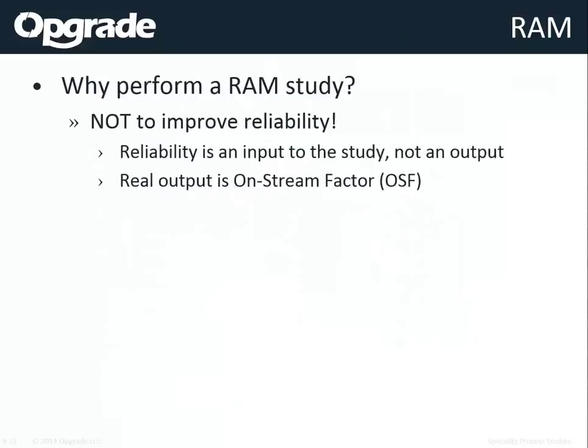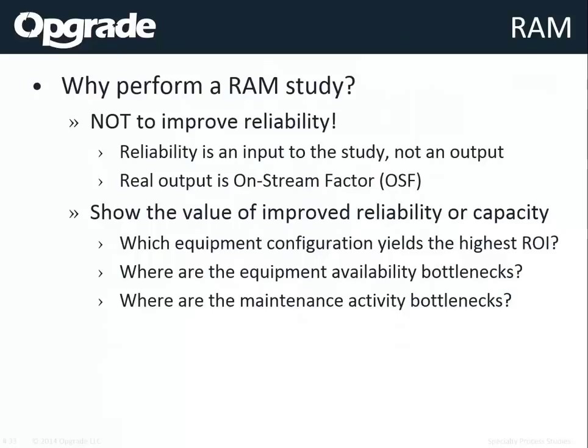With sufficient sample size you can say with some certainty what the mean on-stream factor is — that's the key result of a RAM study. A reliability study is not typically meant to make sure things keep running; usually it's to determine the value of increased reliability, the value of increased capacity, or how much production is lost if capacity decreases.